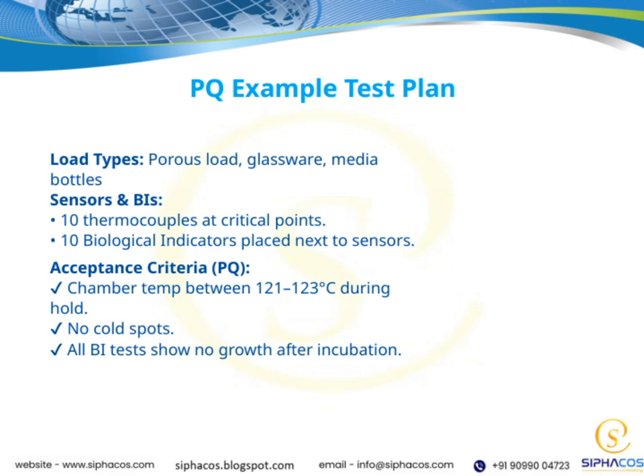Moving on to the acceptance criteria for this performance qualification, or PQ. The key points here are that the chamber temperature must stay between 121 and 123 degrees Celsius during the hold phase. Maintaining this temperature range is crucial for effective sterilization. We also need to ensure there are no cold spots within the chamber, which could compromise the sterilization process. Lastly, all biological indicators should show no growth after incubation, confirming that the sterilization cycle successfully eliminated all microbial life. Overall, this test plan helps us verify that our sterilization process is reliable, consistent, and effective for the loads we typically process.